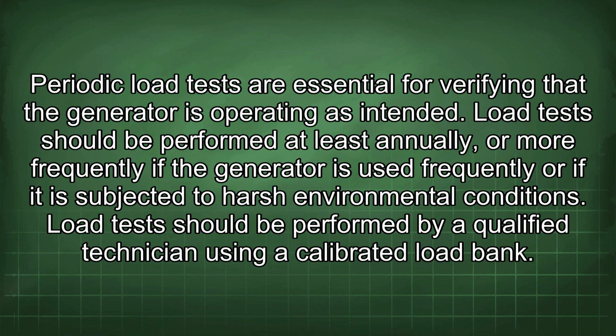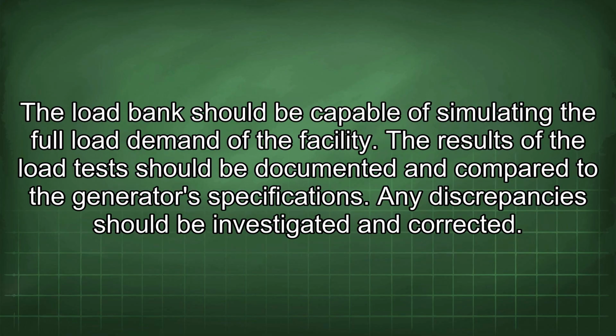Load tests should be performed by a qualified technician using a calibrated load bank. The load bank should be capable of simulating the full load demand of the facility. The results of the load test should be documented and compared to the generator's specifications. Any discrepancy should be investigated and corrected.